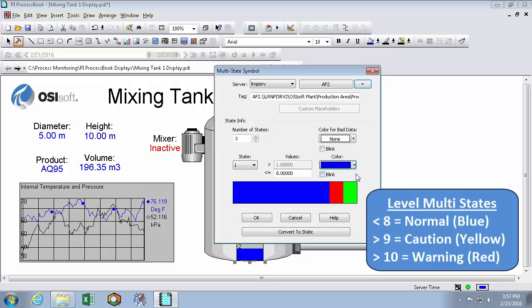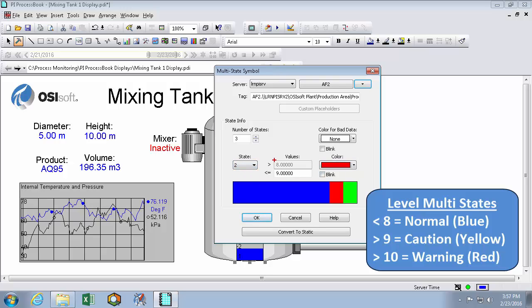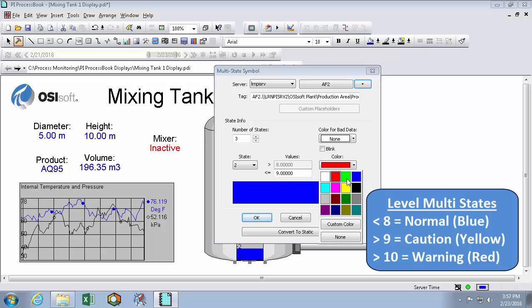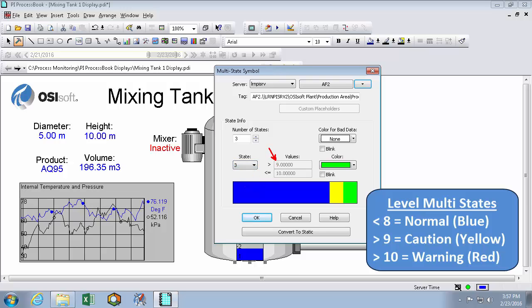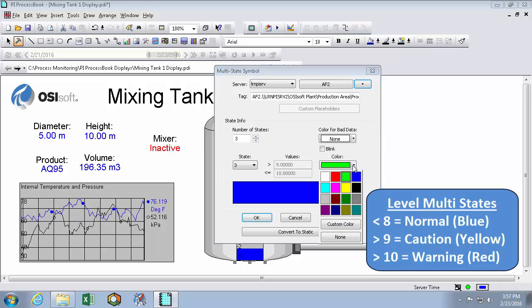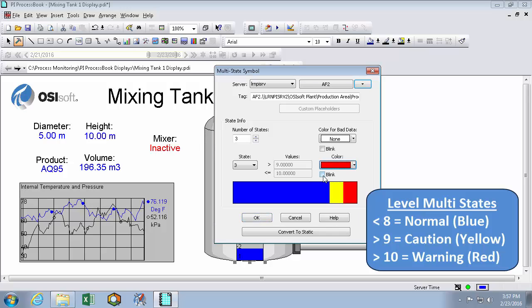The next state, we can see here that the lower bound is set to the previous state's upper bound. And we can change the upper bound. So state 2 will be between 8 and 9 and be yellow. And finally state 3, which is again the lower bound of state 3 is state 2's upper bound. And the upper bound of state 3 is set to the tag's expected maximum value. So I don't need to change these values. But I will change the color change to red and make it blink.